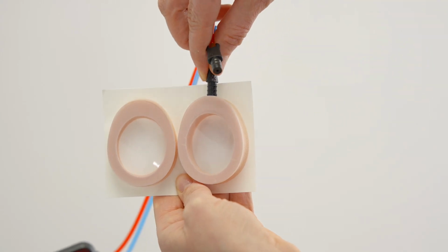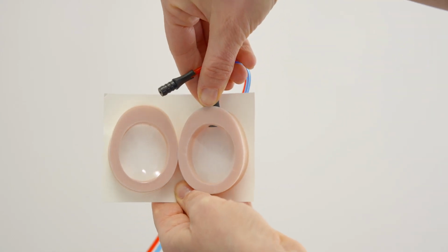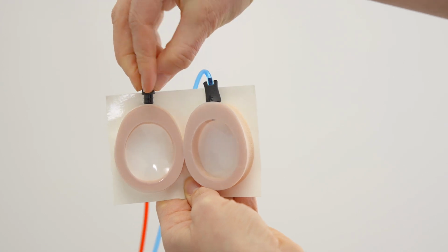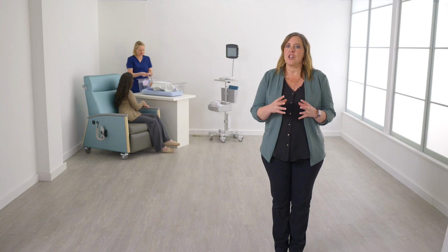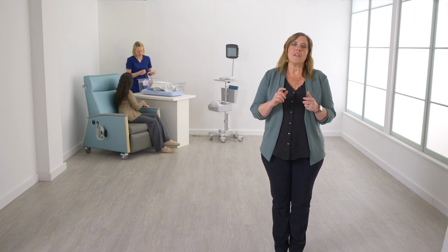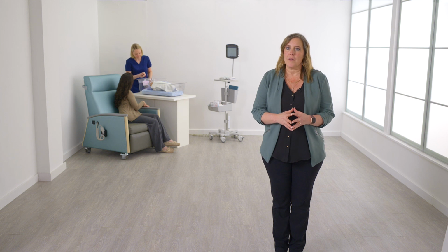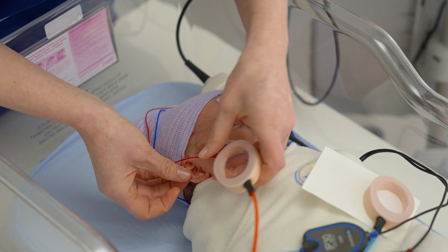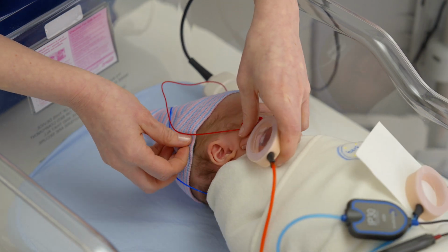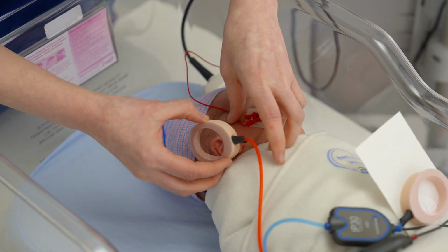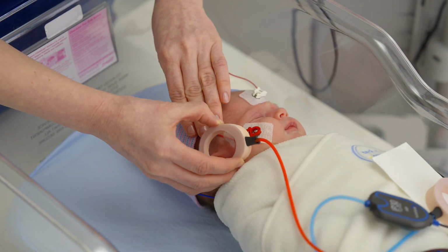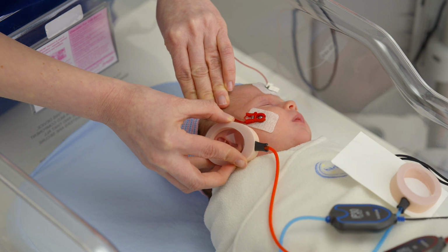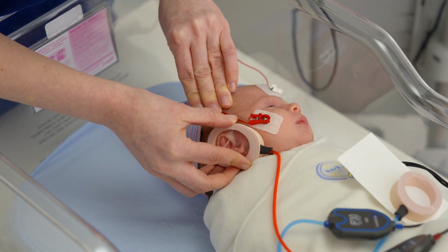When using ear cups, fully insert the black adapter at the end of the red and blue tubing into the opening of the foam. Massage the front of the ear canal and pull down and out on the outer ear to pop the ear canal open. Peel the ear cup attached to the red tubing from the backing card and place it around the baby's right ear. Make sure the black adapter is not blocked by the baby's outer ear. Press around the entire circumference of the ear cup to ensure adhesion to the baby's skin.